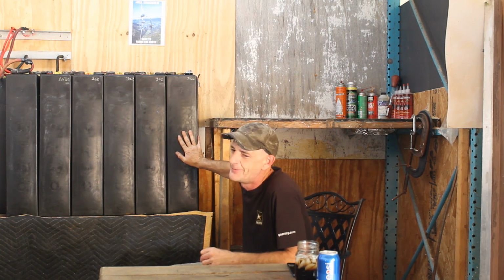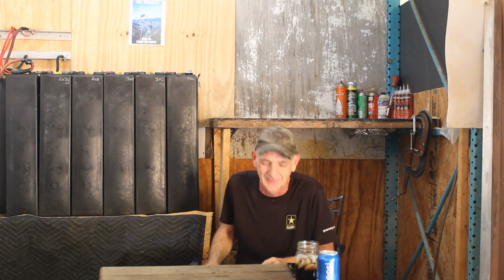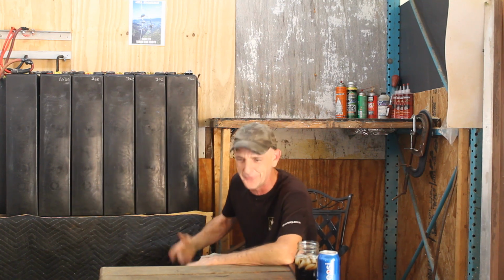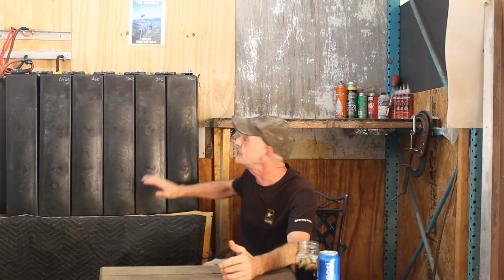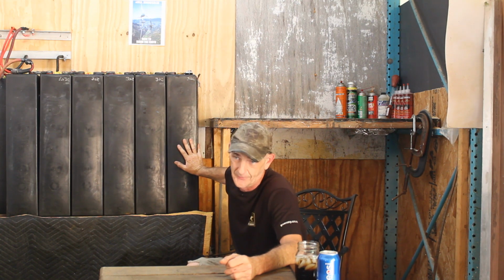Now, the great thing about that is, and this is why many of you who have followed me, I will always make the statement that I get more than the rated capacity. We get more than 57 kilowatt hours. And people on other boards are like, oh, you're a liar, you can't be doing that. Well, yes, you can. What they don't understand is, this is a C6 rated battery. You know, look, not that we don't pull 133 amps per rack, okay? But that's not the going rate. Most of you guys aren't going to pull that either, okay?